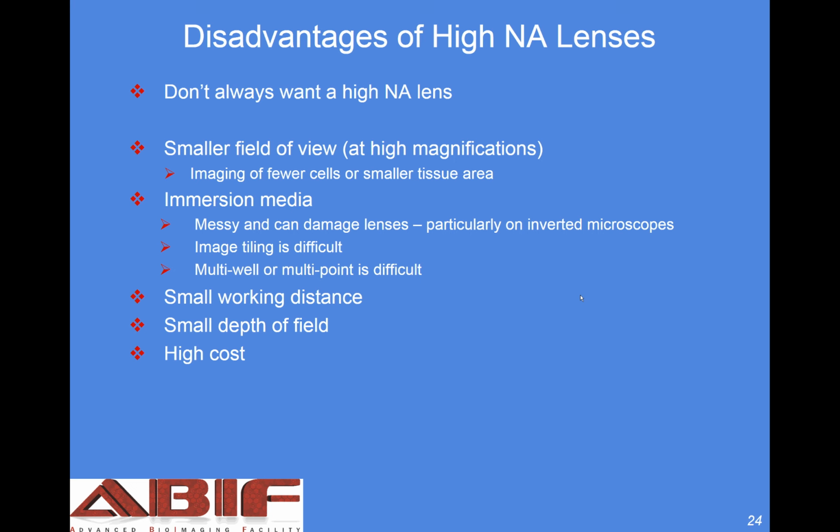Immersion media can be messy and can damage lenses and microscopes, particularly on inverted microscopes. And if you have a large sample and you want to tile, usually the immersion media won't move a large distance with automated tiling. And if you wanted to do, say, an 8-well plate and do 8 experiments, you would have to move manually between wells in order to have enough immersion media for that to work.